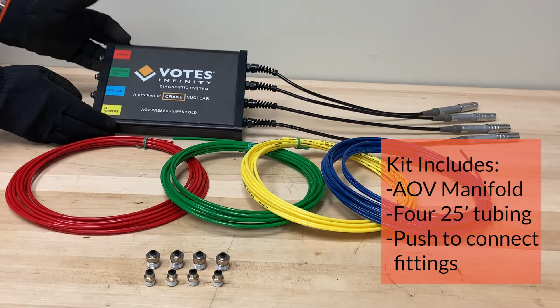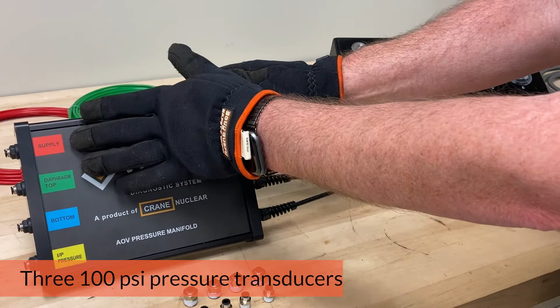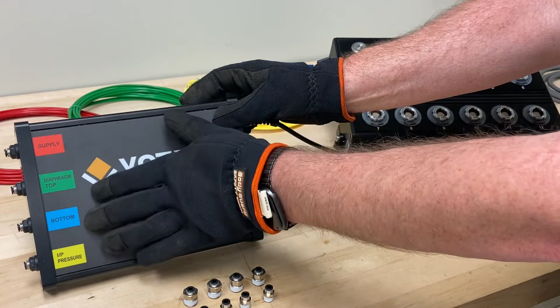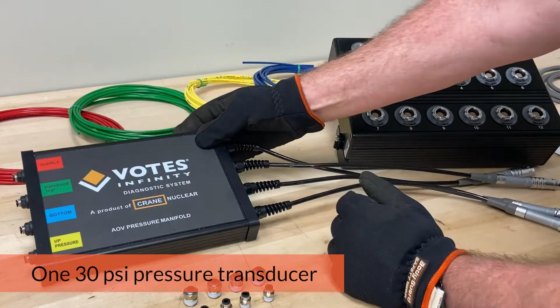With the manifold itself, 25 feet each of red, green, yellow, and blue tubing, as well as a variety of push-to-connect fittings. The AOV manifold comes with three 100 psi pressure transducers for measuring supply and the actuator pressures, either diaphragm or top and bottom, depending, as well as a 30 psi transducer for measuring I to P pressure, control pressure. If your control pressure is higher than 30, you can use one of the other transducers for that measurement if needed.